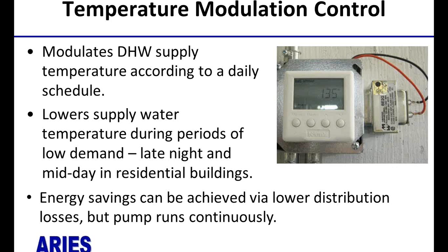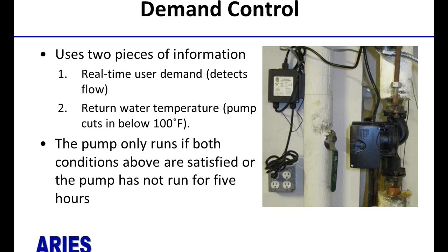A third type of control is temperature modulation control. And this doesn't control the pump, but it controls the supply set point. And based on a schedule, it increases the supply temperature during peak times and reduces it during off-peak times. So energy can be saved by having a lower overall water temperature and reducing the heat loss through the pipes that way. But the pump does run continuously.